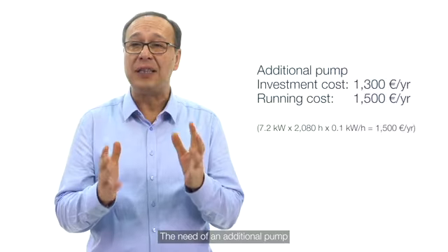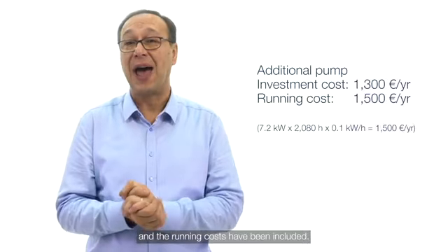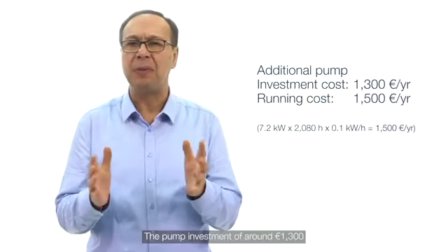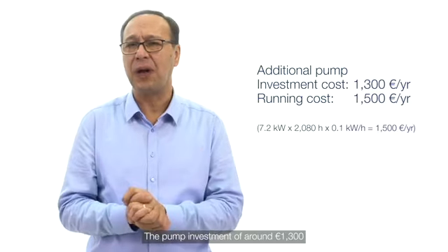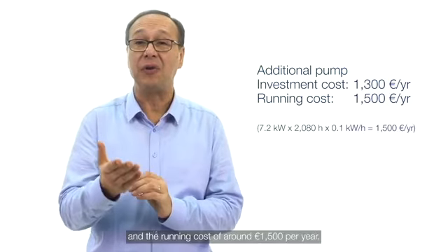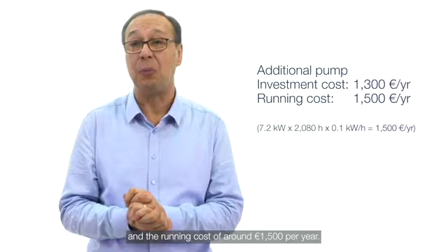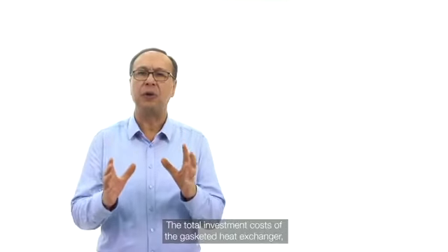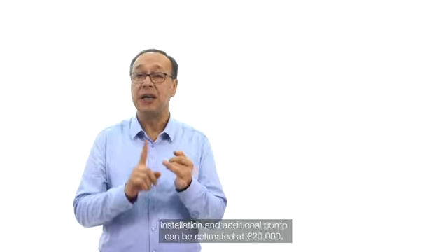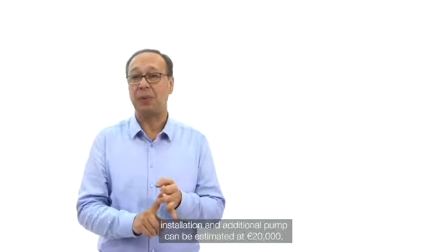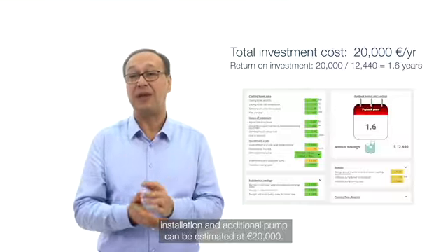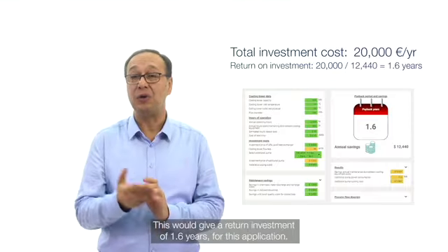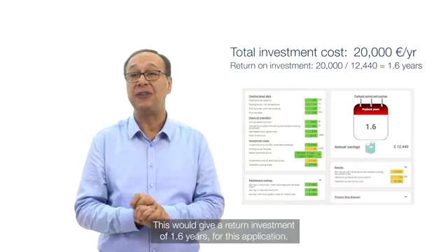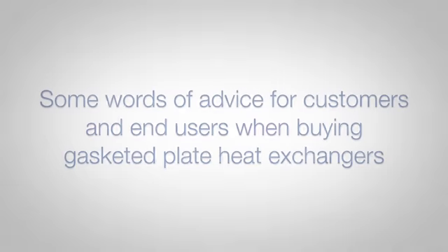The need of an additional pump and the running cost have been included. The pump investment of around €1,300 and the running cost of around €1,500 per year. The total investment cost of the gasketed heat exchanger, installation and additional pump can be estimated at €20,000, and this would give a return on investment of 1.6 years for this application.